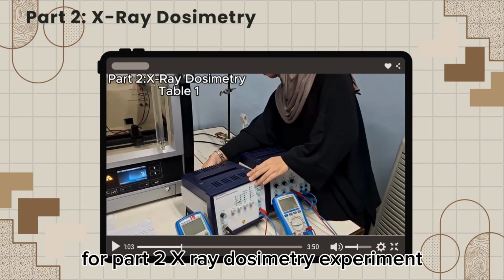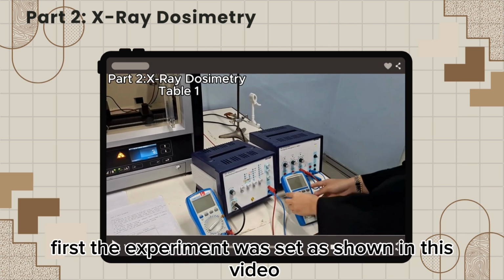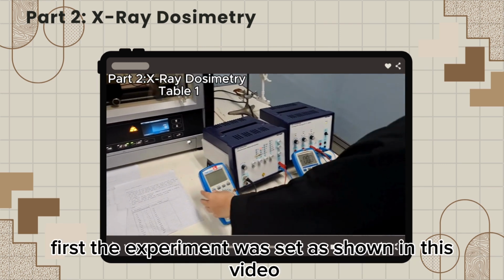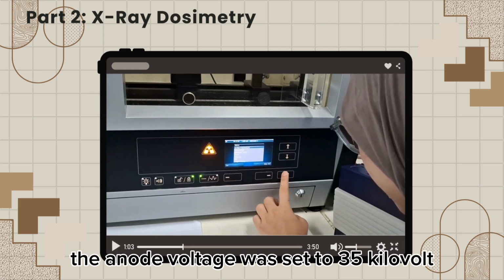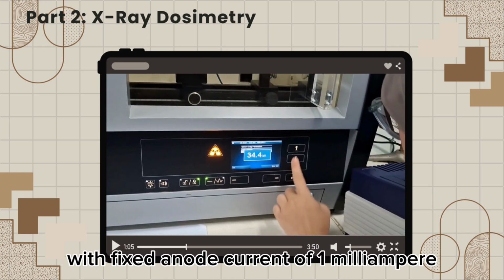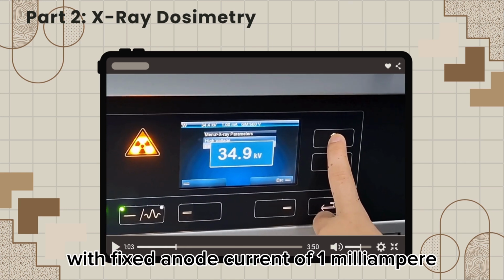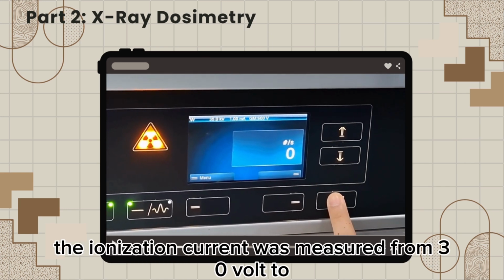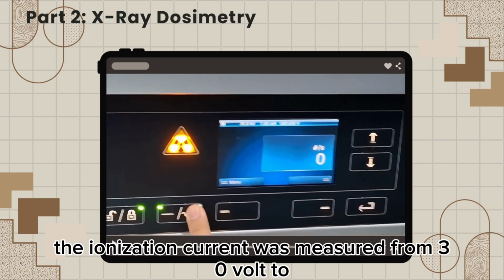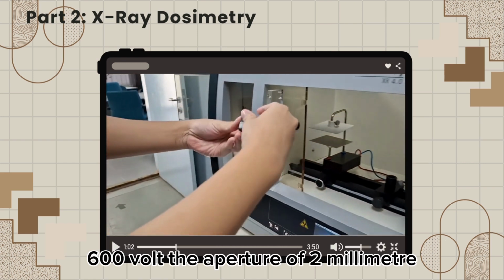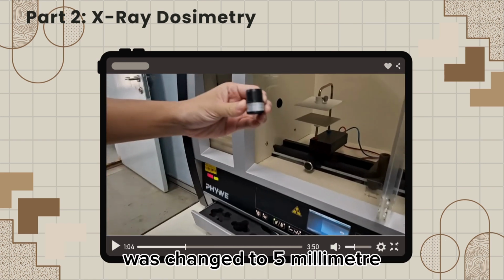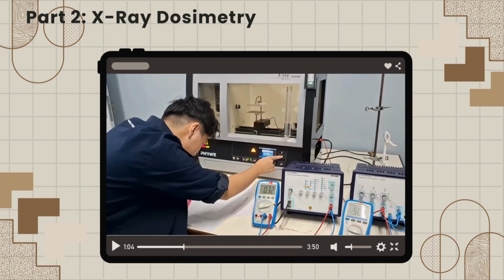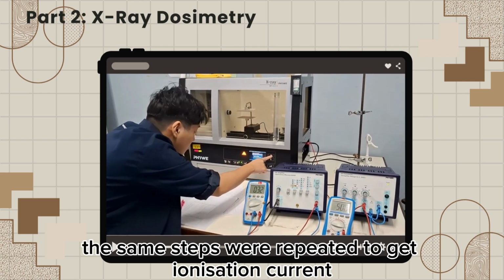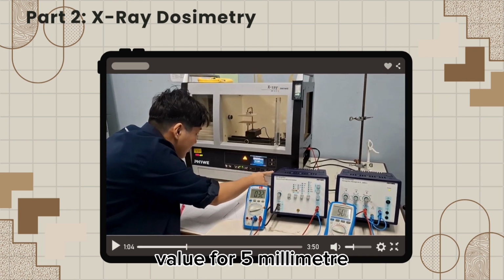For the part 2 X-ray dosimetry experiment, first, the experiment was set up as shown in this video. The anode voltage was set to 35 kV with a fixed anode current of 1 mA. For table 1, the ionization current was measured from 30 V to 600 V. The aperture of 2 mm was changed to 5 mm. The same steps were repeated to get the ionization current values for 5 mm.